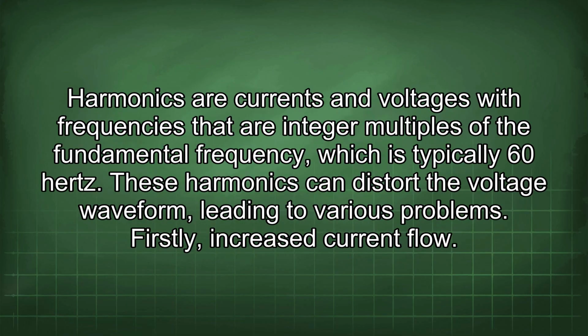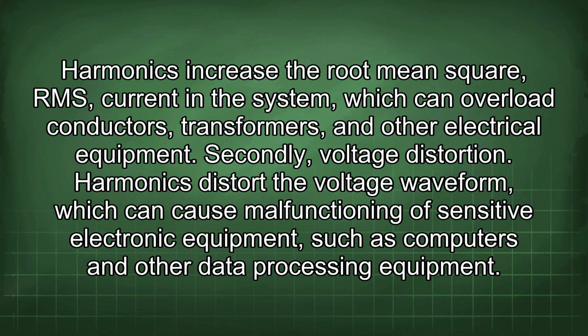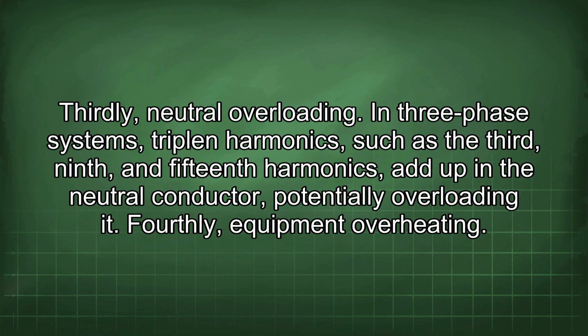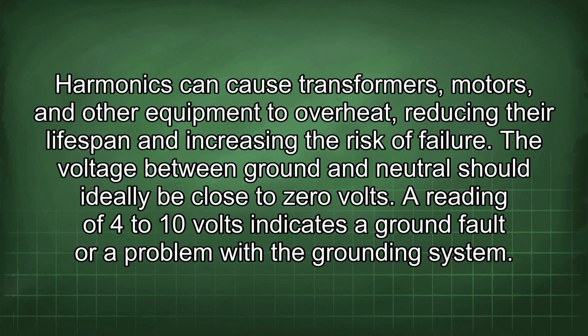The presence of harmonics is another significant concern, especially with a high concentration of nonlinear loads such as computers. Harmonics are currents and voltages with frequencies that are integer multiples of the fundamental frequency, which is typically 60 Hz. These harmonics can distort the voltage waveform, leading to various problems. Firstly, increased current flow. Harmonics increase the root mean square (RMS) current in the system, which can overload conductors, transformers, and other electrical equipment. Secondly, voltage distortion. Harmonics distort the voltage waveform, which can cause malfunctioning of sensitive electronic equipment, such as computers and other data processing equipment. Thirdly, neutral overloading. In three-phase systems, triplen harmonics, such as the 3rd, 9th, and 15th harmonics, add up in the neutral conductor, potentially overloading it. Fourthly, equipment overheating. Harmonics can cause transformers, motors, and other equipment to overheat, reducing their lifespan and increasing the risk of failure.